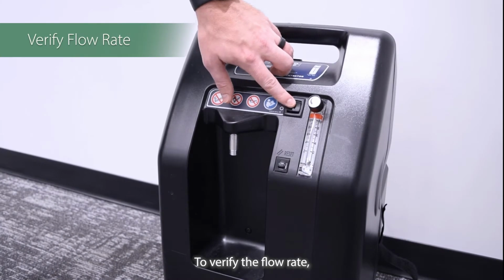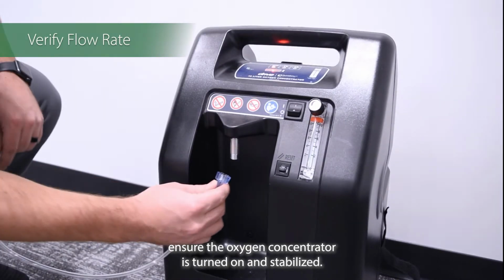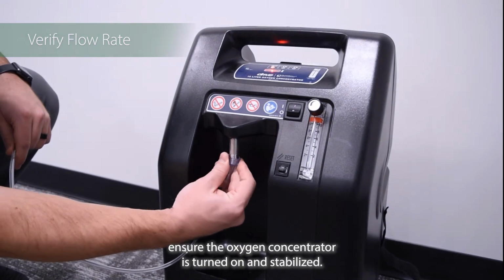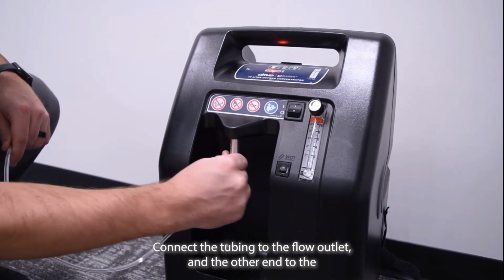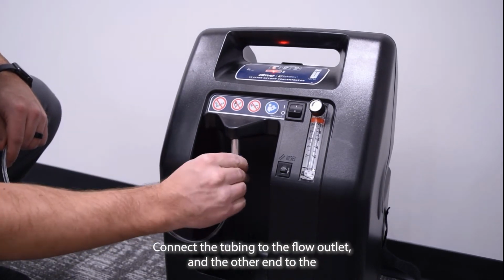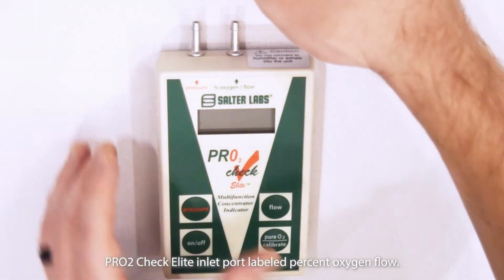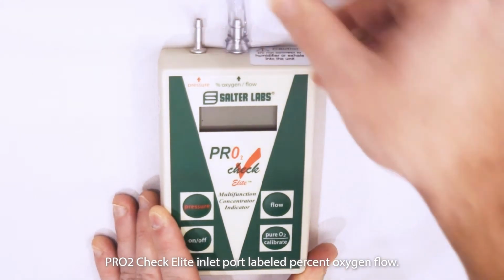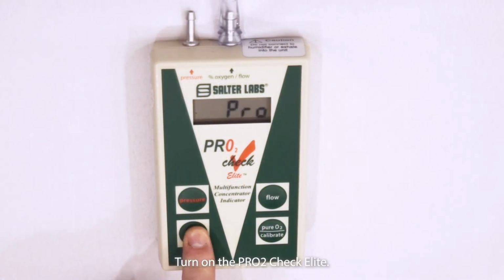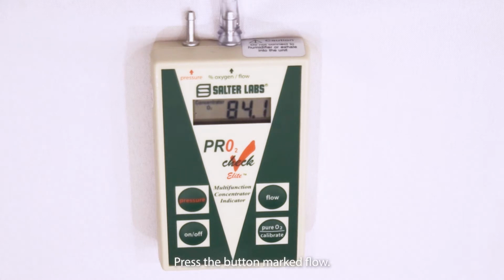To verify the flow rate, ensure the oxygen concentrator is turned on and stabilized. Connect the tubing to the flow outlet and the other end to the PRO2 Check Elite inlet port labeled % oxygen flow. Turn on the PRO2 Check Elite. Press the button marked Flow. The LCD will display a numeric value indicating the flow output in liters per minute.